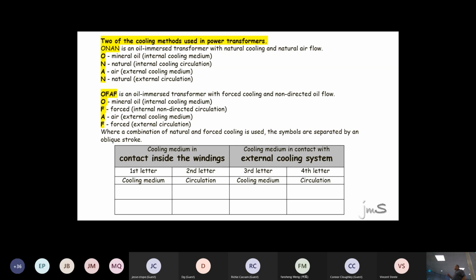Something important you need to know: the first two letters refer to the inside cooling method of a transformer, not outside. The second two letters refer to the cooling method on the outside of the transformer. So firstly, the first two letters.